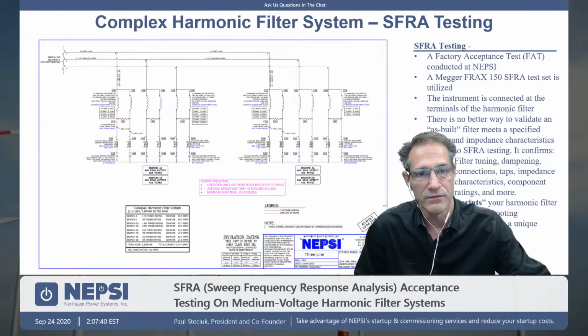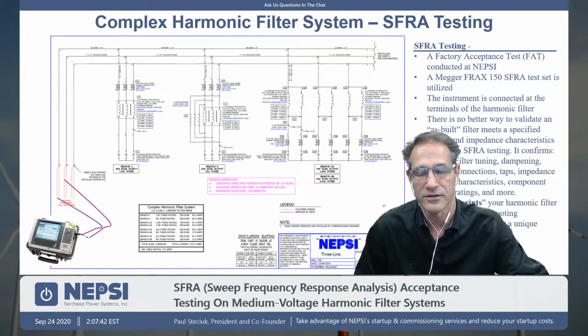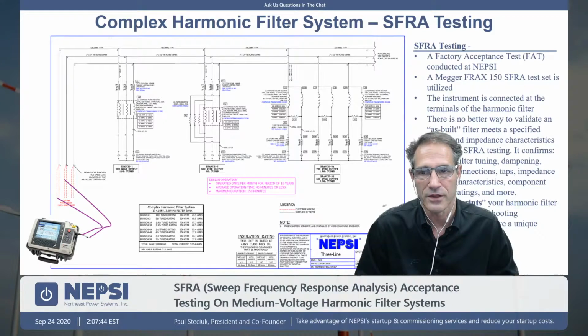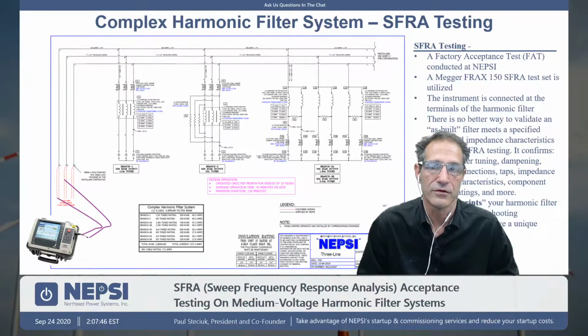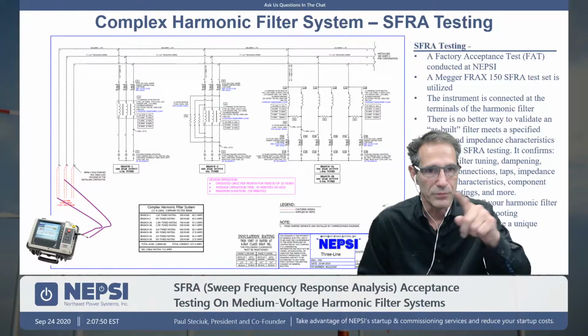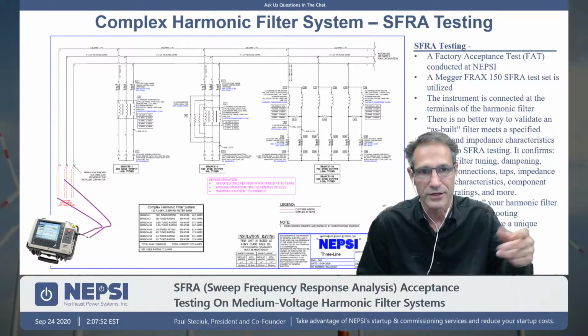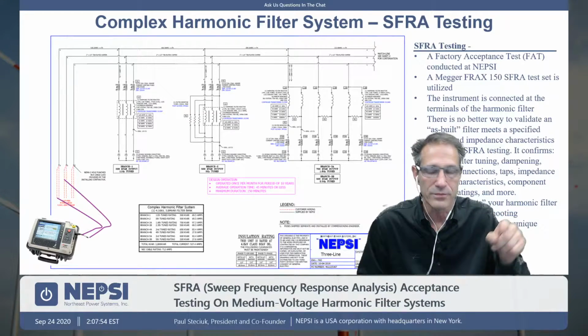Well, we believe that SFRA testing is by far the best way to test a harmonic filter system. Connect it at the terminals and check, well, what does the impedance profile look like? And we're going to show this today. But what does that impedance profile look like?